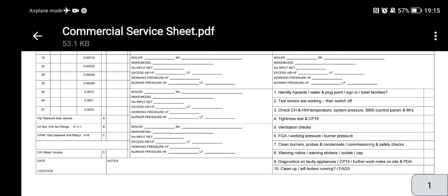That's if the boiler has low rate as well. You can also do your working pressure, but that's best done once you've worked on all the boilers so you can run them at the same time. Endeavor to get all the boilers on simultaneously to get a working pressure reading. In certain circumstances it's also good to get a flue reading with all boilers running — for instance, during flue dilution checks on a common flue — to see what combustion readings you get.